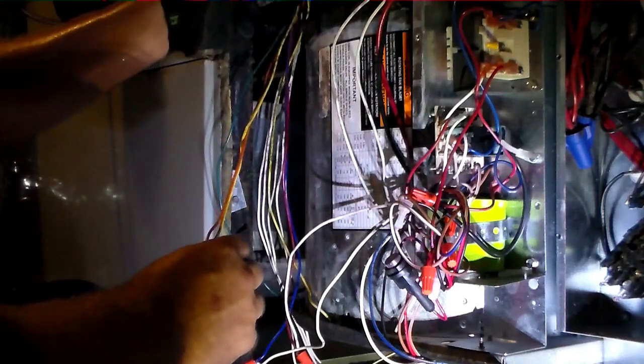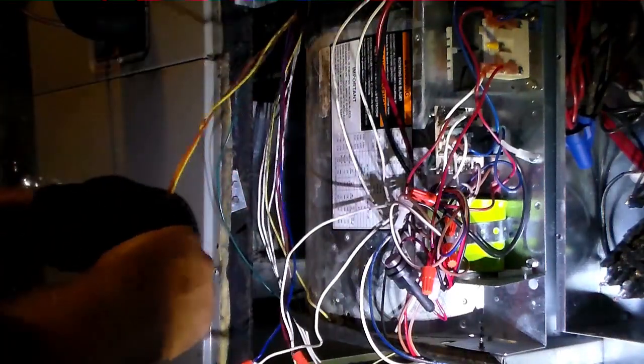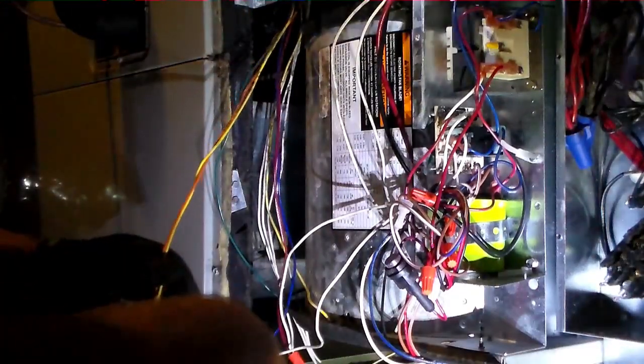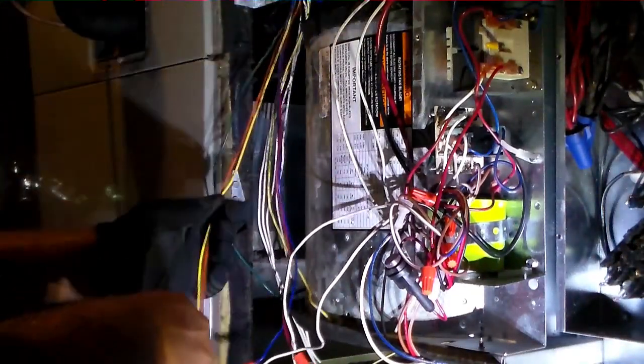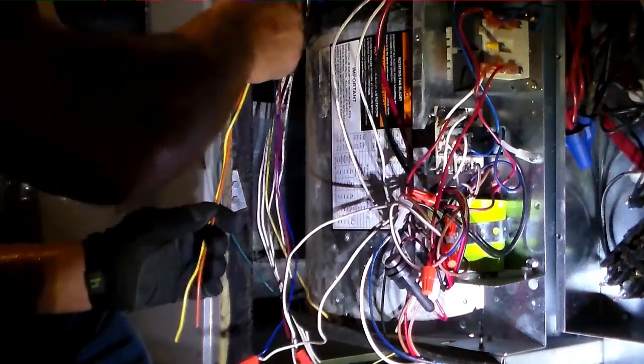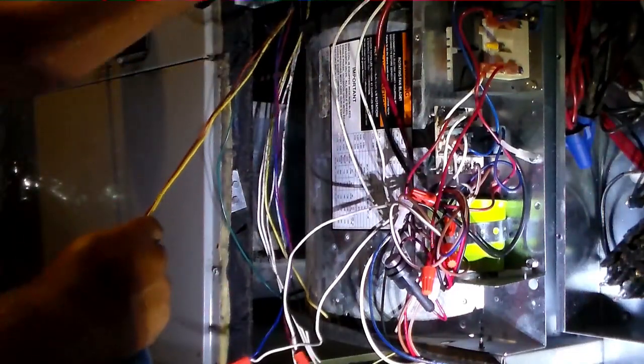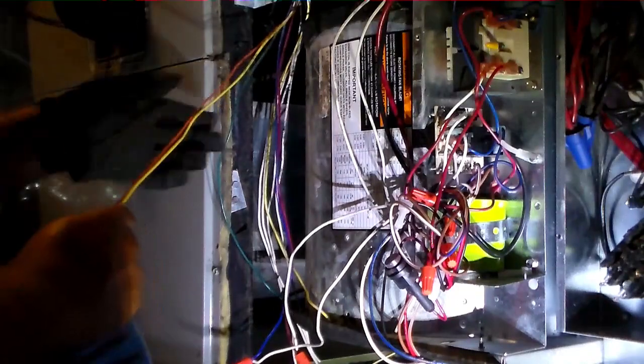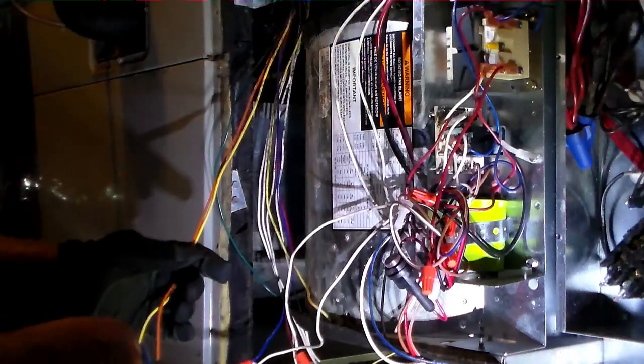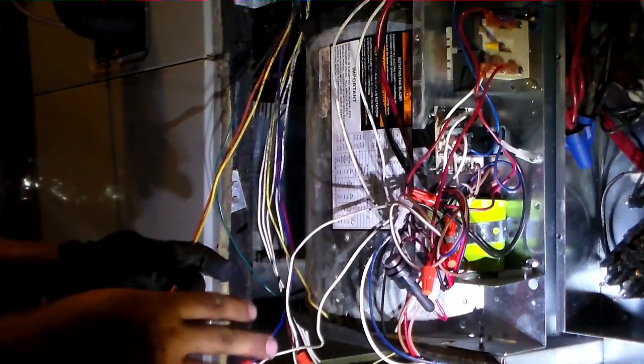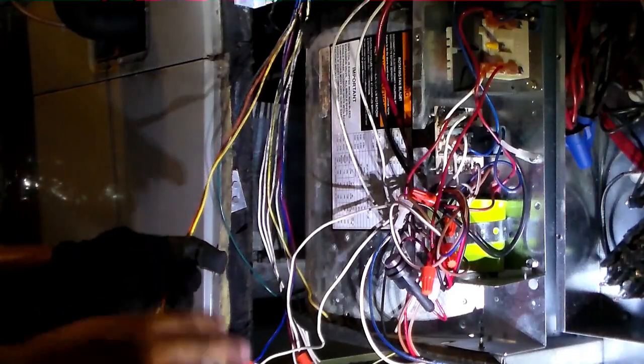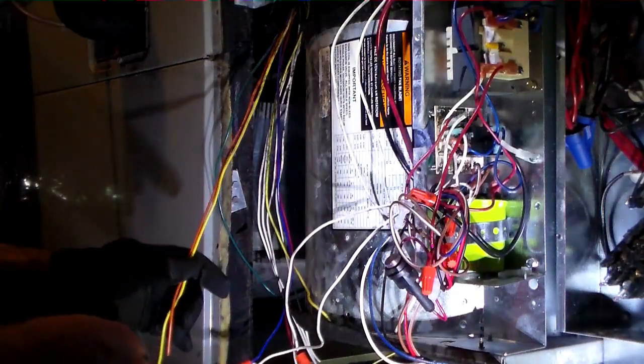Okay, so most of our wiring is off to the side over here. We don't need the Y wire because we're not telling a variable speed motor to run at a certain speed. So really all we need is red and white and blue and green, and that is all we require.